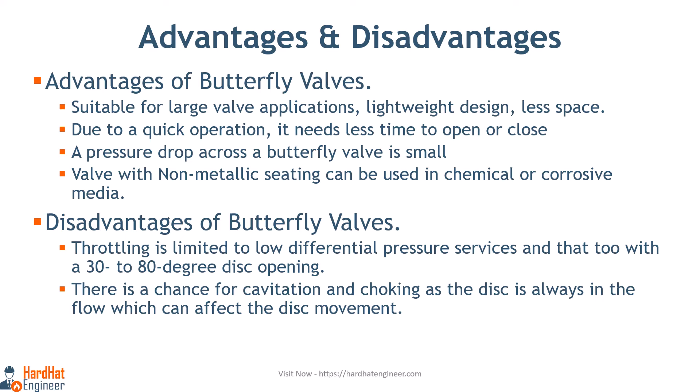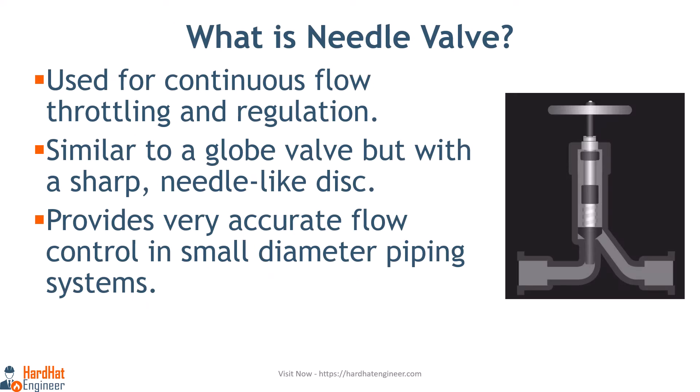Disadvantages of butterfly valve: throttling is limited to low differential pressure services with a 30 to 80 degree disc opening. There is a chance of cavitation and choking, as the disc is always in the flow, which can affect disc movement.